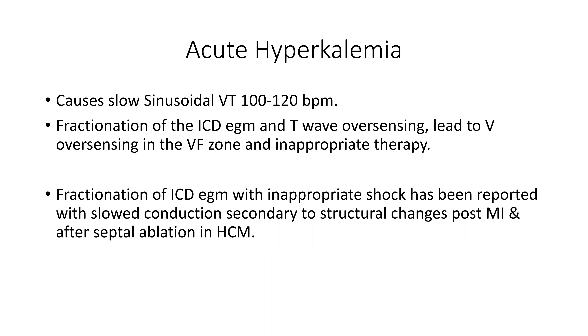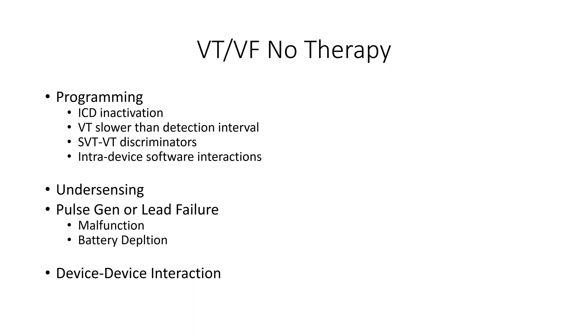So patients in VF and no therapy occurs. What are the causes? Well, part of it's programming: if we inactivate the ICD, if the VTach is slower than detection, if we have issues with discriminators, and if there is intra-device software interactions. Undersensing is a big problem, especially when the R wave, that's why we want the R wave sensing to be above 5. Pulse generator lead failure, and then device interacting with another type of stimulator.